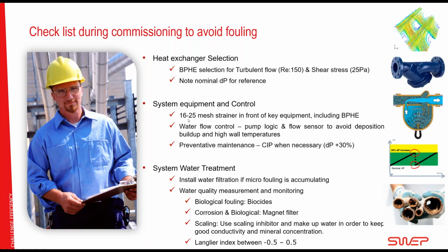The weak spot for the brazed plate and the plate and frame is the blockage, the macro fouling, as I call it. The best way is to have a strainer. Stop it before it goes in. If you get it in the ports, then that's a good starting point for the rest of the fouling, and it's so easy. Make sure that you have the flow that you think you have. If you plan it for 10 GPM but you have no clue if you have 1, 10, or 100, you are asking for problems, because normally, if you don't know, it's 1, not 100.